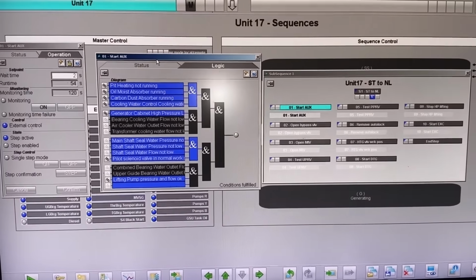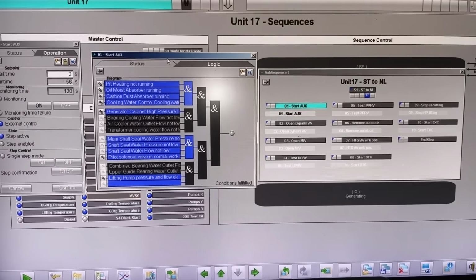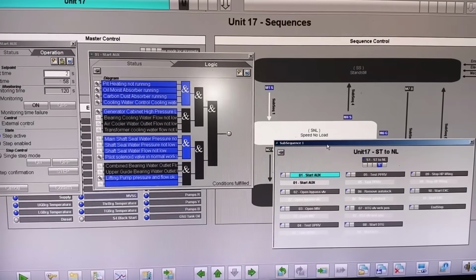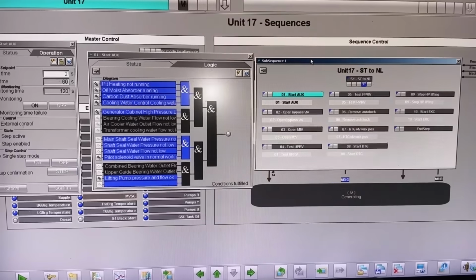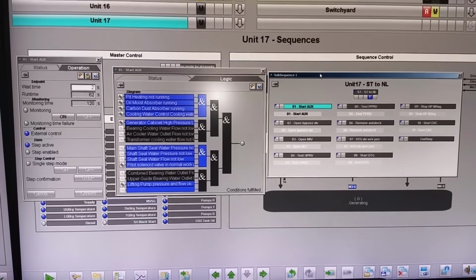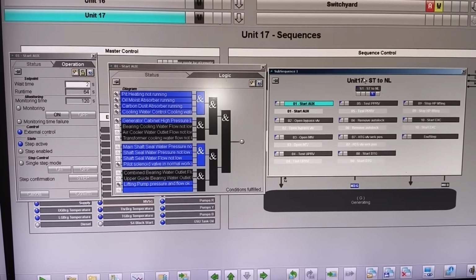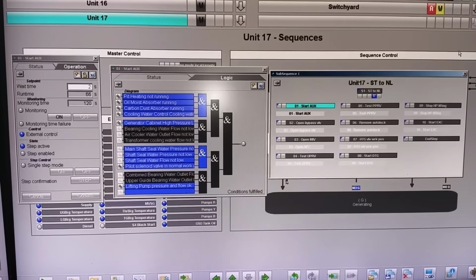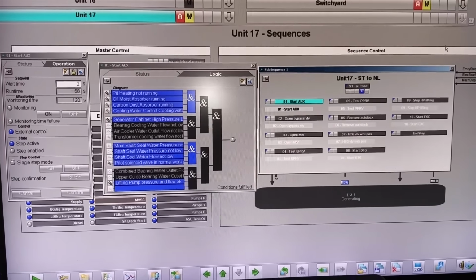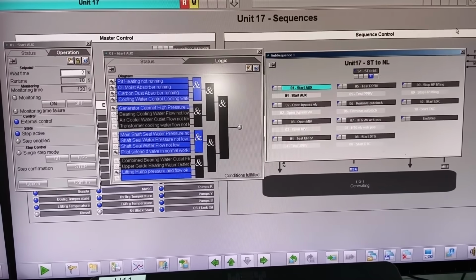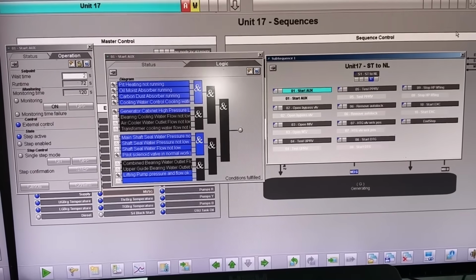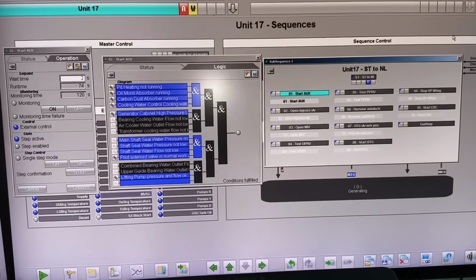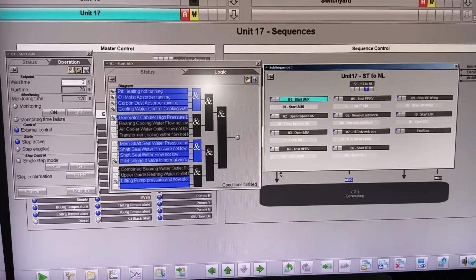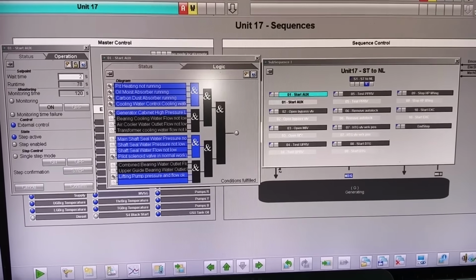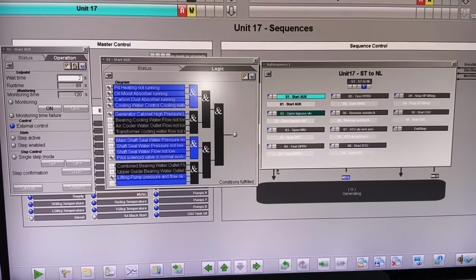Watch the screen carefully as every system starts one by one. And before rotation begins, the high pressure oil lifting system injects oil beneath the rotor to create a microscopic oil film that slightly lifts the 100-ton shaft off the thrust bearing pads. This prevents metal-to-metal contact and protects the bearing from severe startup damage. Only after every auxiliary parameter becomes healthy does the control logic allow the sequence to continue.